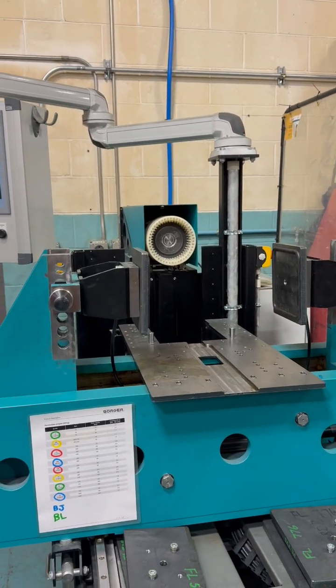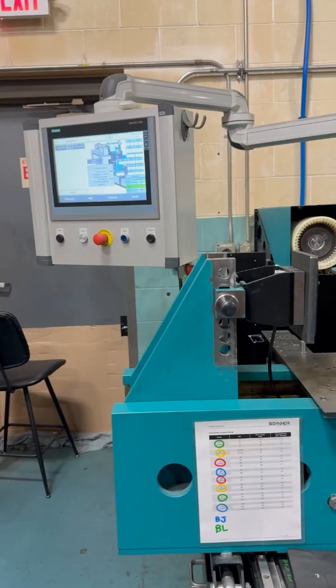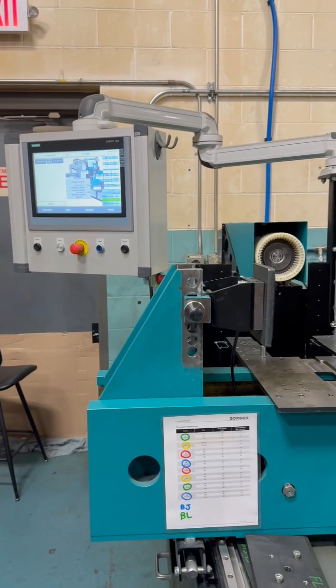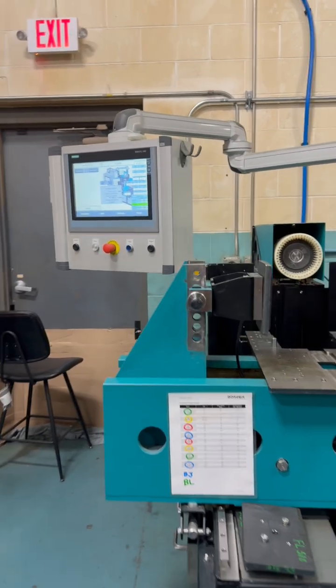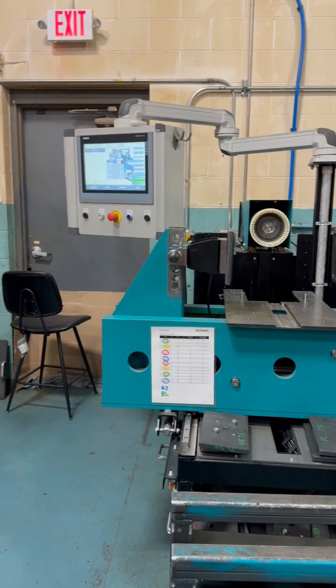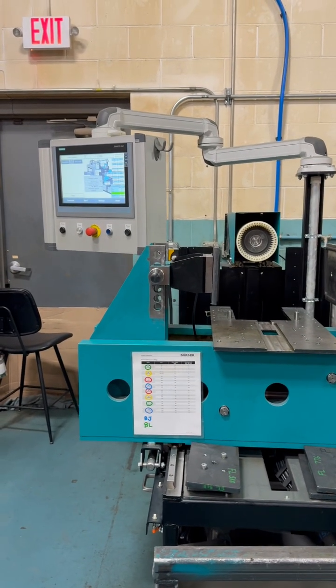In our case, if we're doing a retrofit of mechanical seals or rotors, we put it back on the FAT machine to verify integrity of the mechanical seals, as well as the torque rotation, so we can produce a completed document to prove the pump is tested.